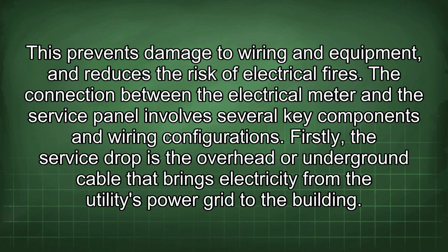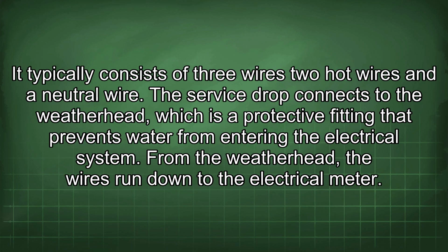The connection between the electrical meter and the service panel involves several key components and wiring configurations. Firstly, the service drop is the overhead or underground cable that brings electricity from the utility's power grid to the building. It typically consists of 3 wires, 2 hot wires, and a neutral wire. The service drop connects to the weatherhead, which is a protective fitting that prevents water from entering the electrical system. From the weatherhead, the wires run down to the electrical meter.